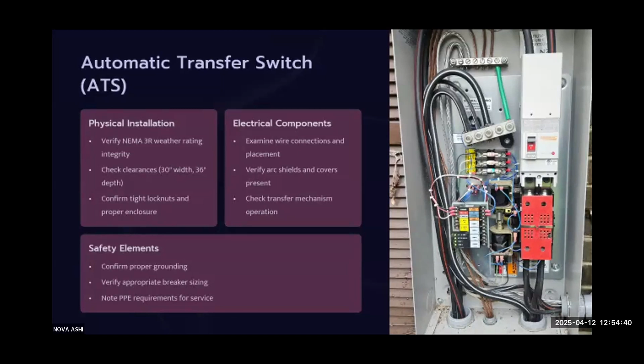Yes. So if I understand correctly, in the existing home, you've got the existing ground, it's usually tied back to the main panel. Yes. Now you put in a generator and an ATS. If I'm hearing you properly, you actually should disconnect that ground at the main panel and reroute everything to the ATS, so the single point of ground is at the ATS?